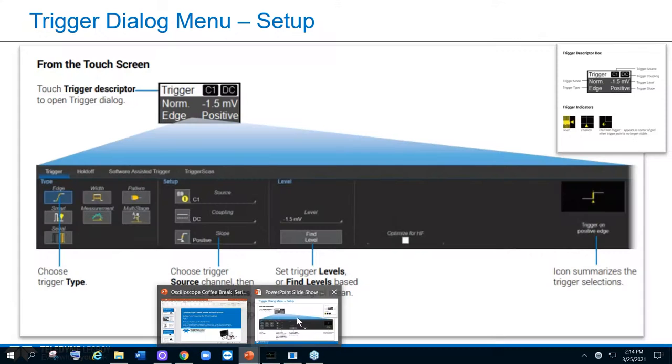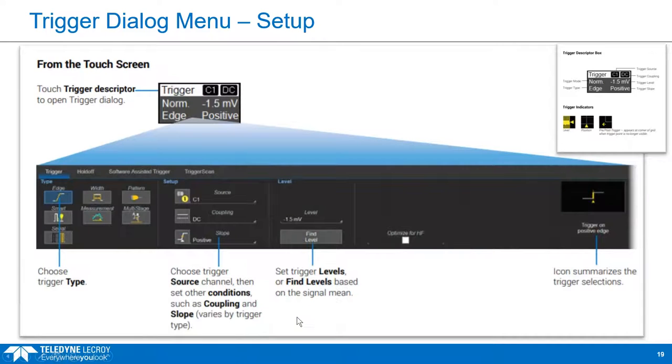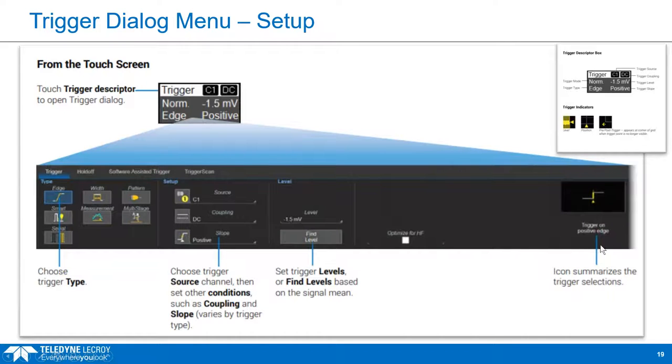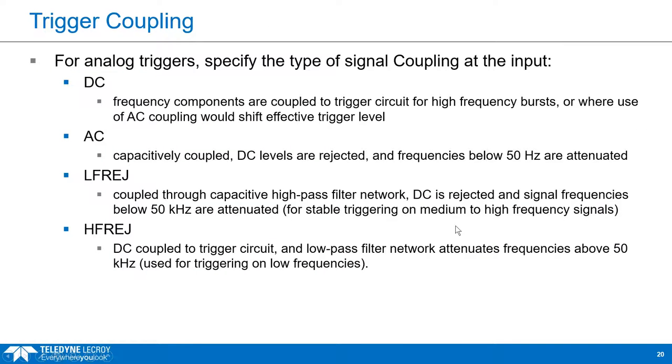So any analog, your digital signals can be utilized here as your source coupling. We have AC, DC, low frequency and high frequency reject. I do want, I just have a slide on that that I want to point out to you that something might be, you know, just a little reminder about that positive, negative and trigger level is here. Within the PowerPoint now, I, this is, as I follow this flow, these are the, this is the trigger dialogue menu briefly. There is off to the right, by the way, there is a little icon that describes what your trigger type is. And that's off display to the right. Here's a little thing on trigger coupling.